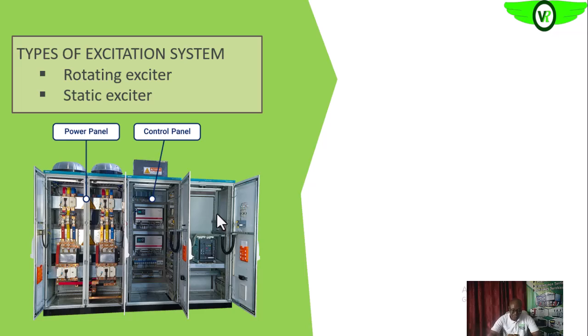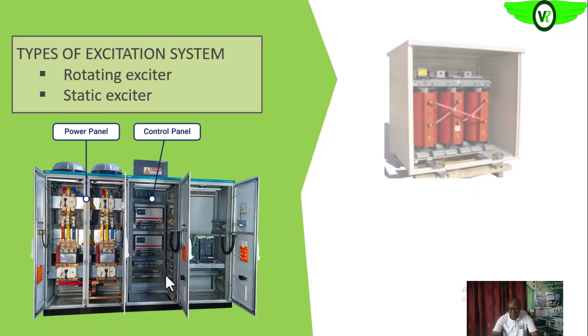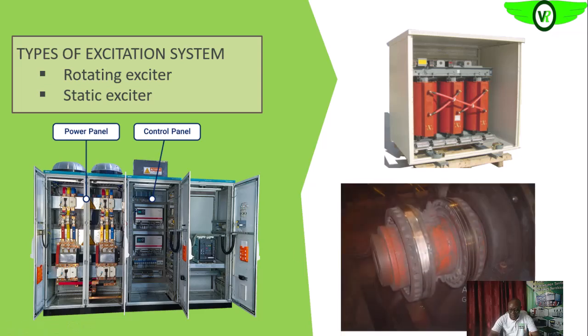So now the static excitation system that we talked about, like we said earlier, is made of electronic circuitry, semiconductor devices that help to convert the AC that comes into it into DC, as we saw in the case of the rectifier bridge on the rotating excitation system. So this is the main power panel that receives power from the excitation transformer, as we'll see later. Then here is the control panel. The output from this unit is sent into the main field via these slip rings, as you can see here. So this brush and slip ring arrangement is what will take the power from this static excitation unit to the main field itself.